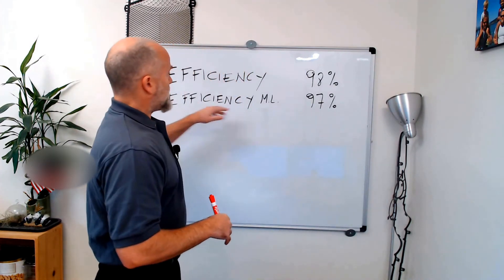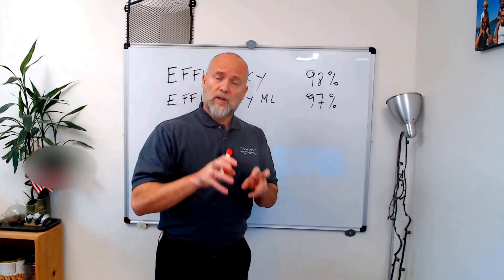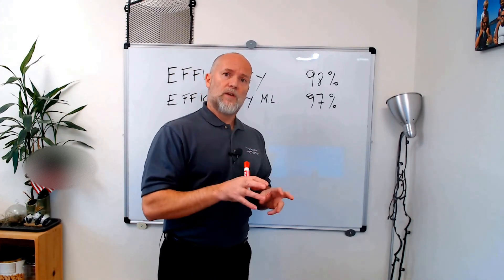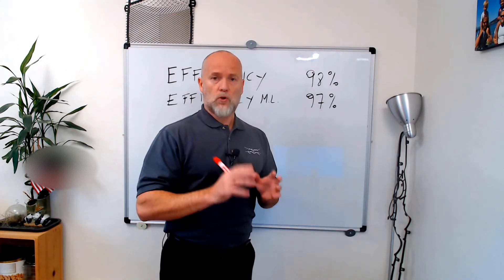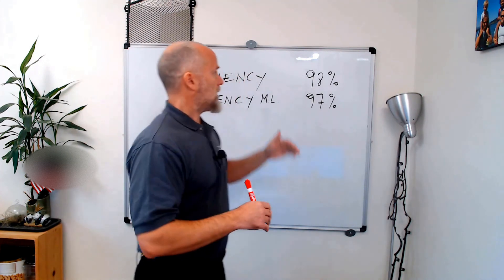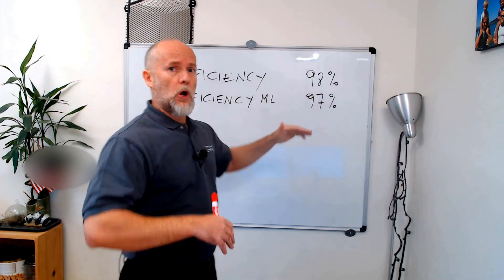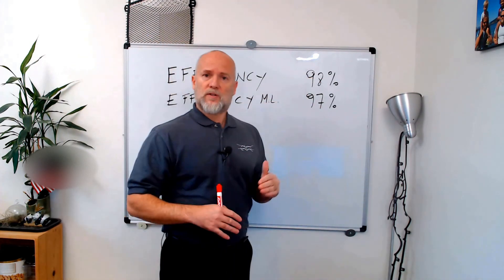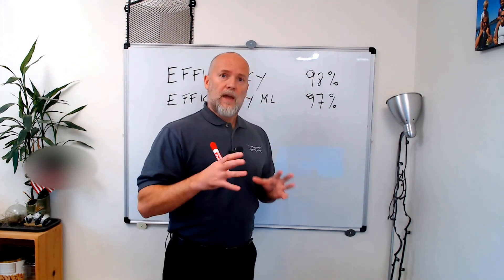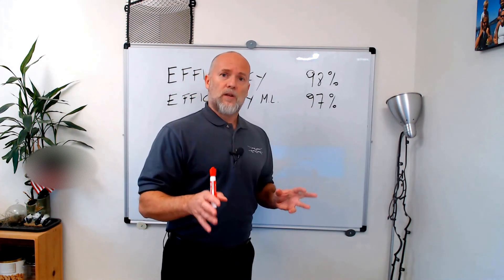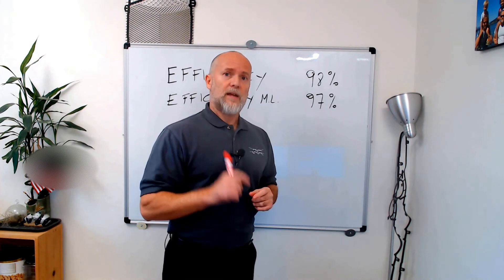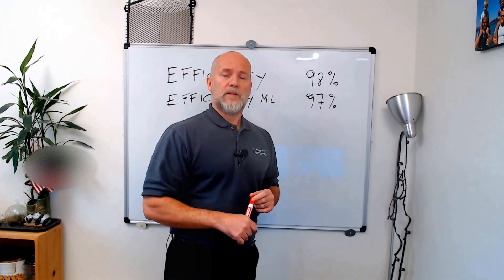The efficiency machine learning is the current efficiency of your heat exchanger compared to the efficiency that the heat exchanger had when it was new, so clean. The algorithm compares these two efficiencies all the time and when they go below a certain threshold, it actually activates an alarm and it tells you that that is the right time to run a CIP cycle.